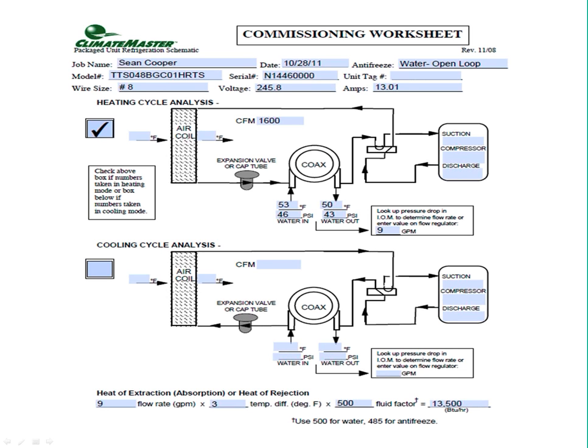Now this unit is open loop. It's using the raw water. Open loop, we can use about 2 gallons per minute per ton. This unit needs about 8 GPM. It's pumping 9. It's probably okay.